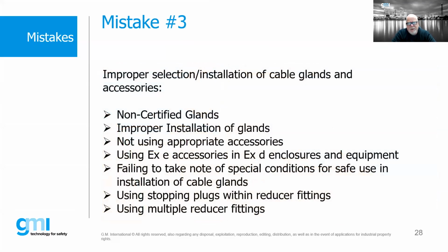The third mistake is improper selection and installation of cable glands and accessories. Some of the pictures jump around, but things like non-certified glands, improper installation of glands, not using appropriate accessories, using Ex e accessories with Ex d enclosures and equipment can be an issue. Also failing to note special conditions for safe use, using stopping plugs within reducer fittings, which is very common and not allowed, and using multiple reducer fittings.